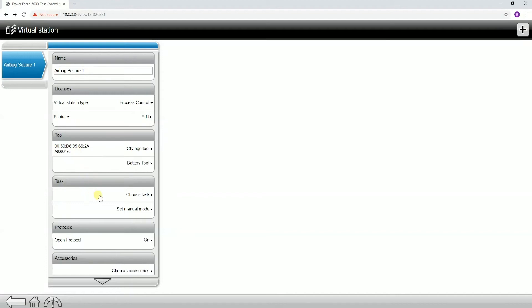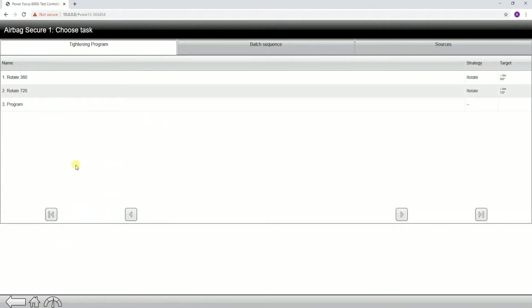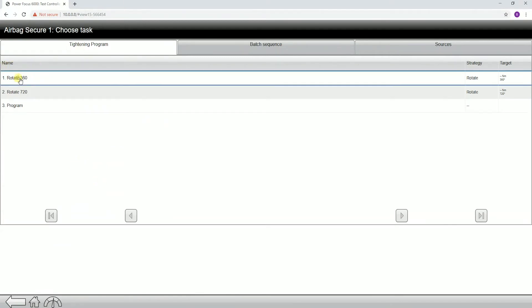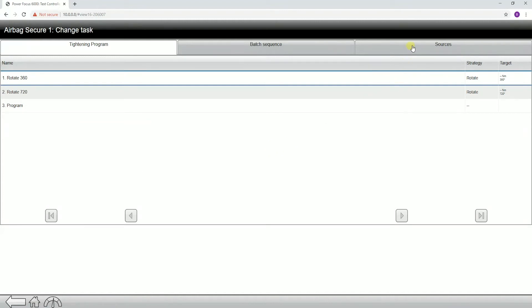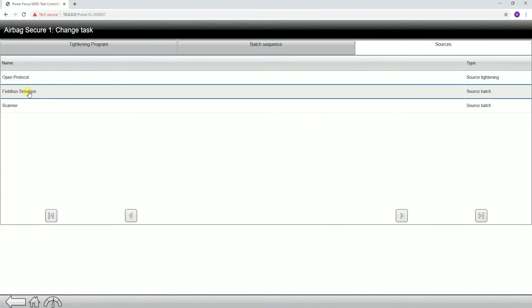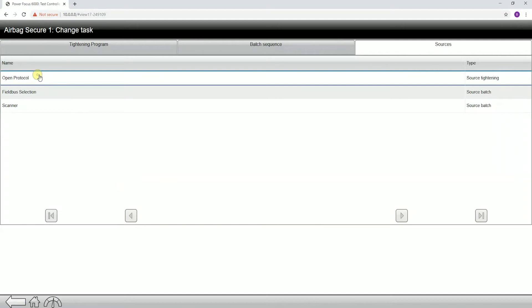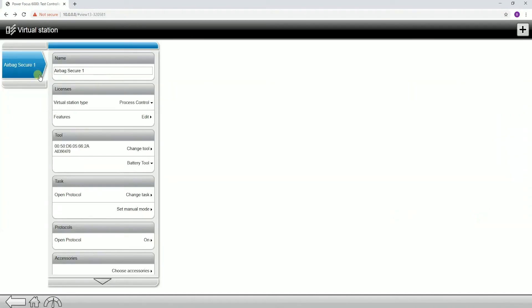Next tab down, we're going to have our task. This is one of the most important pieces of the Power Focus 6000 — this is telling the tool what to do. If you click in to choose tasks, we have a couple of options. We can select a tightening program and just run it all day long. If we wanted to select from a field bus, we'd go to our sources menu and select field bus selection. If we wanted to select a tightening program over open protocol, we'd select the source created in the sources tab. The task is going to be telling the tool exactly what it's supposed to do.